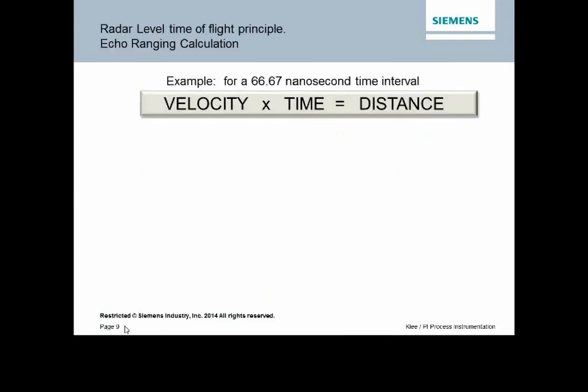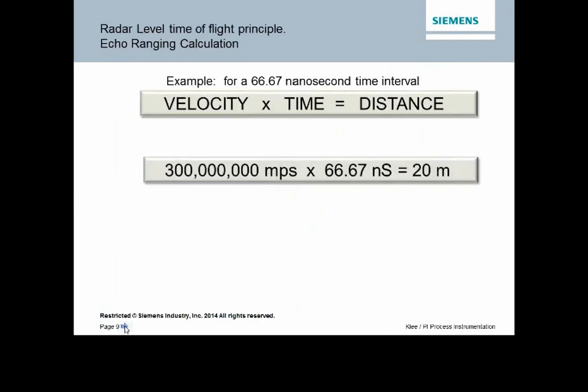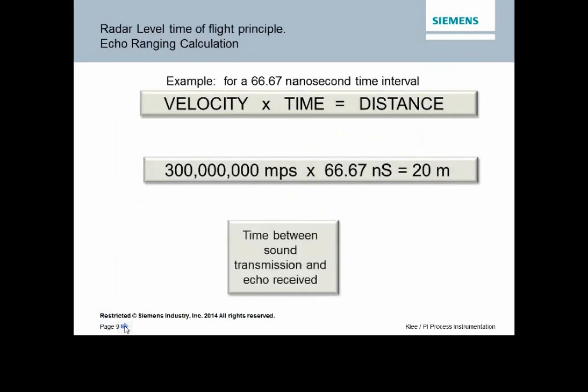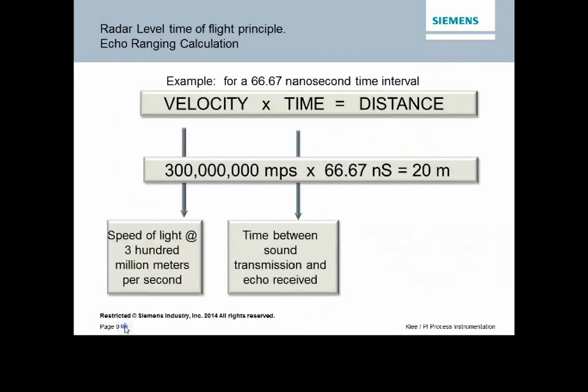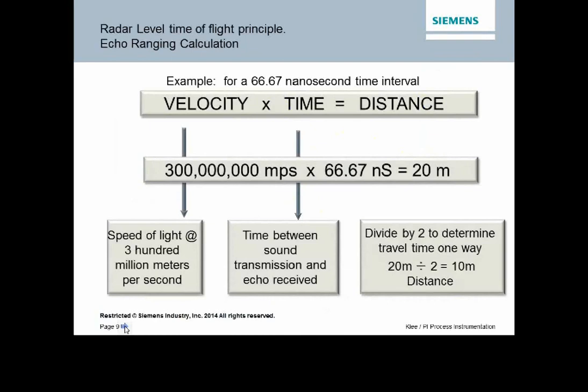Quickly here, the level time of flight principle. We use an echo ranging calculation. If we know how fast we're going and we know how long we've gone, we can develop the distance. When it comes to radar, we're working at the speed of light, which happens to be just under 300 million meters per second. So what we do is actually measure the time of flight, the time between the signal transmission and the echo received. That time times the speed of light gives the time for the radar echo to go to the material surface and back, so we divide it by 2 to get the actual correct measurement. What we look at is the time of flight times the speed of light, and then we divide it by 2 to get it right.